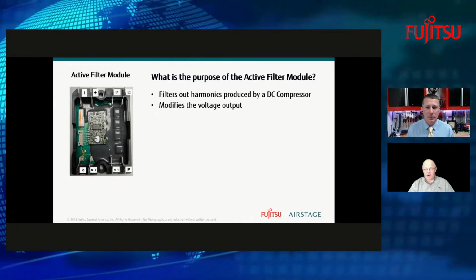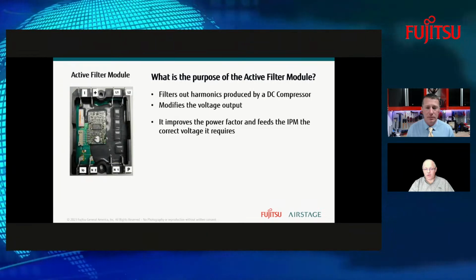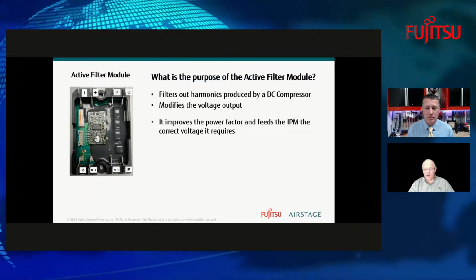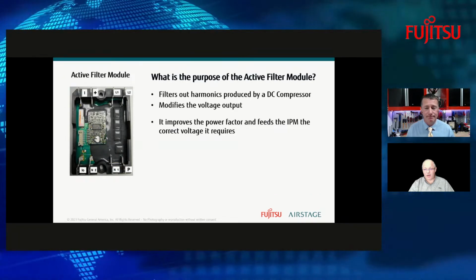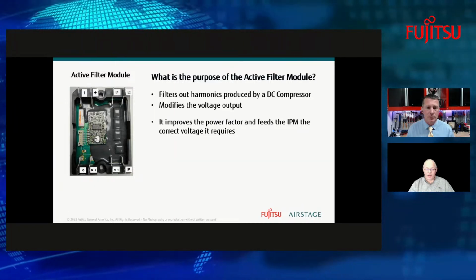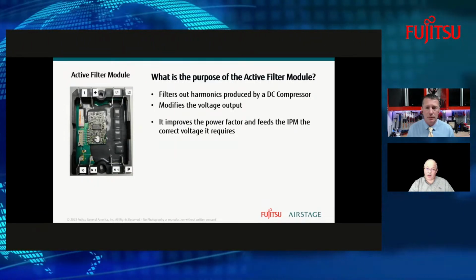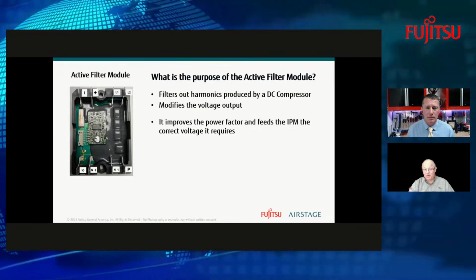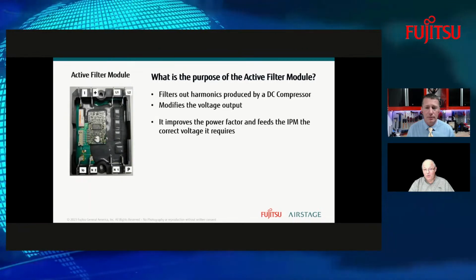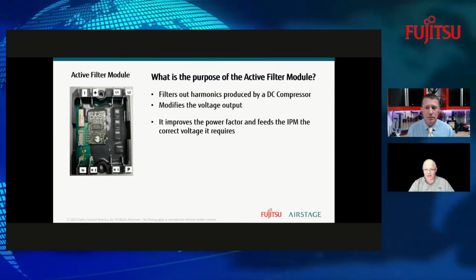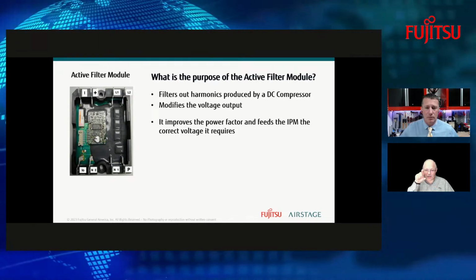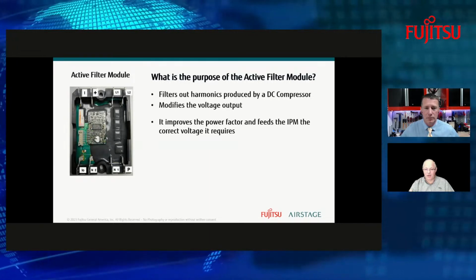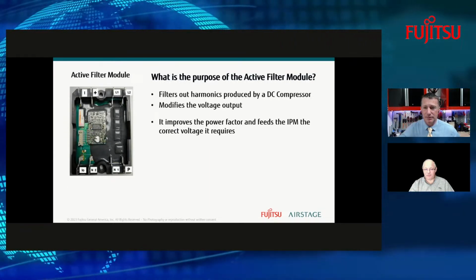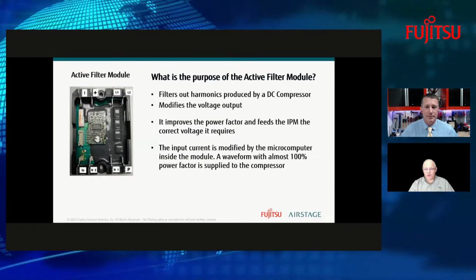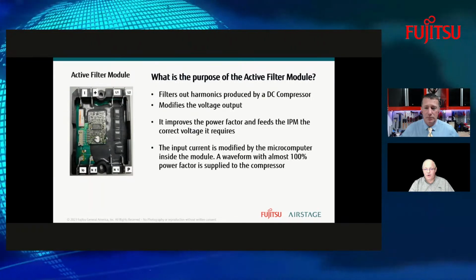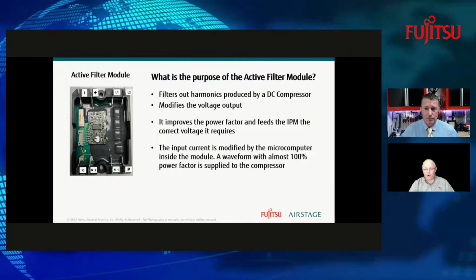It also does other things like modify the voltage output, and we're also looking to improve the power factor. The better the power factor, the more efficient and clean the signal is going to be going to the other components. So it's important that you have a device like that. Now, this also gets very hot. If you were to look on the back side of this active filter module, you would see a metal plate. That metal plate on the back side is where you put all of your heat sink paste. And the two holes you see there would screw that down to the aluminum heat sink itself. So the entire module is part of your heat dissipation. Right. Nice. And so what we're doing is modifying the input current, and we're really attempting to get a 100% power factor.